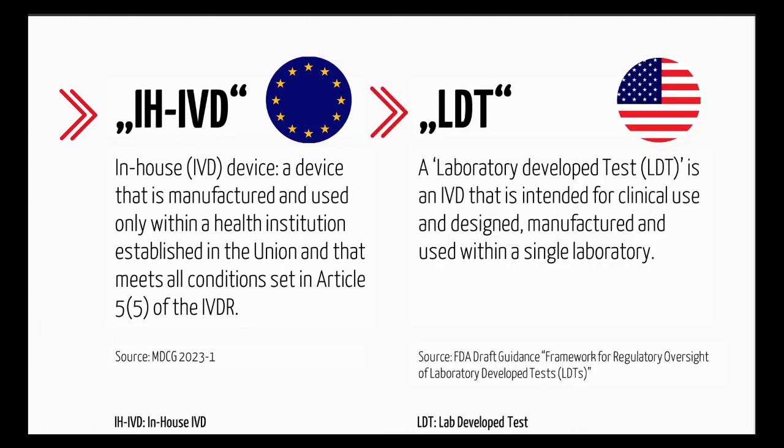And in the US, this is called a laboratory developed test. A laboratory developed test is an IVD that is intended for clinical use and designed, manufactured, and used within a single laboratory. So pretty much the same definition, but not referring to particular articles or requirements.